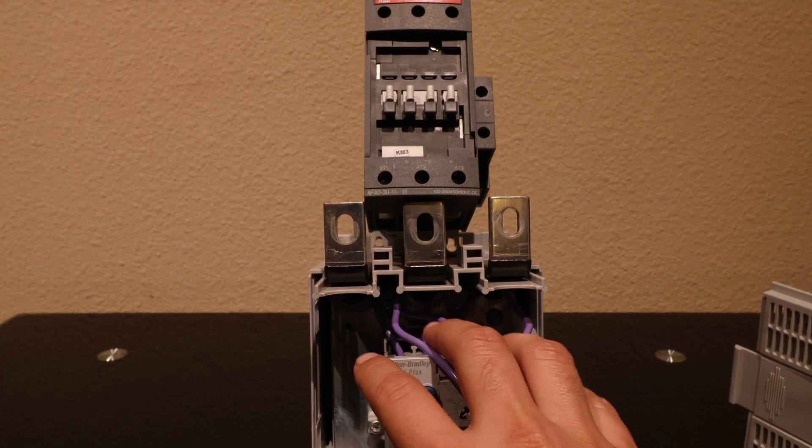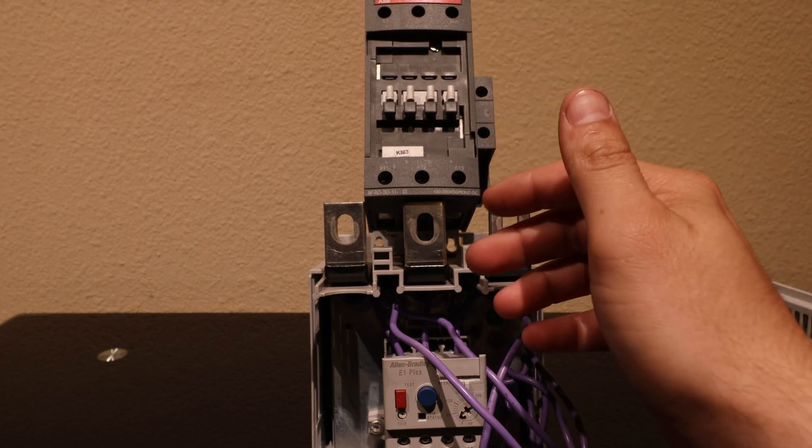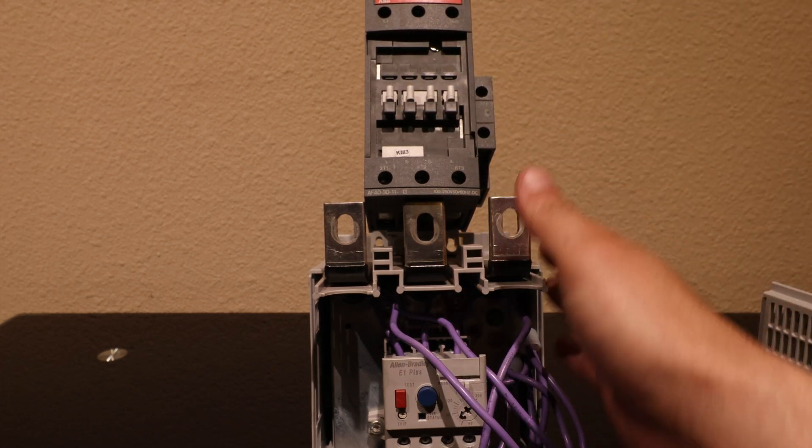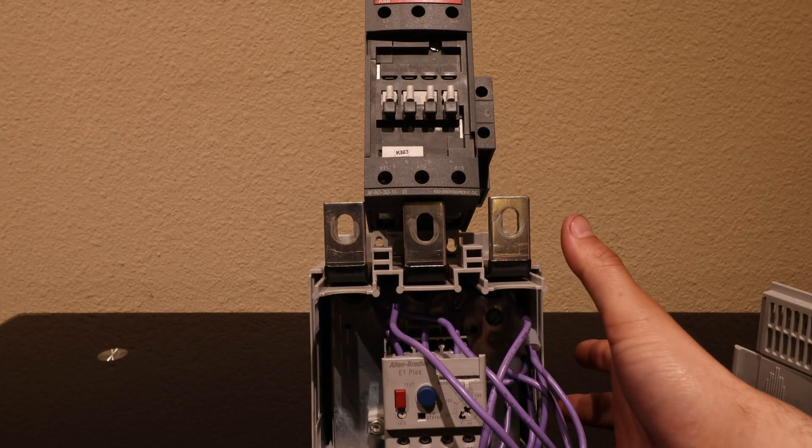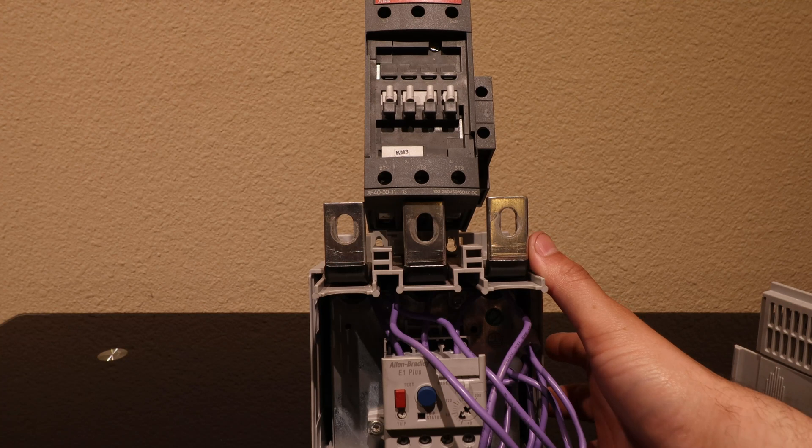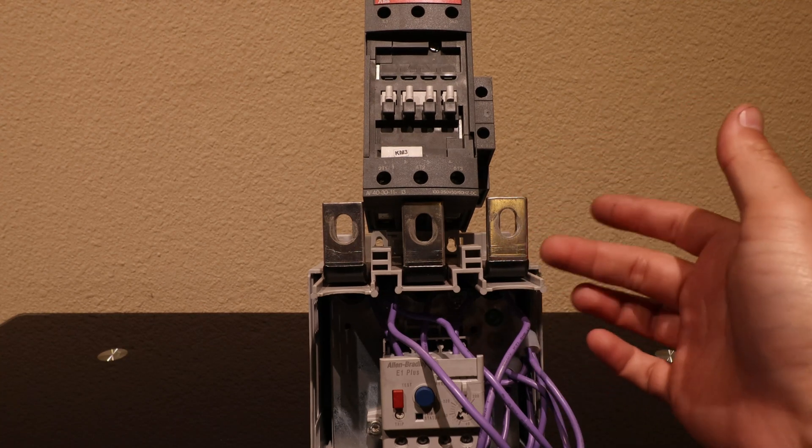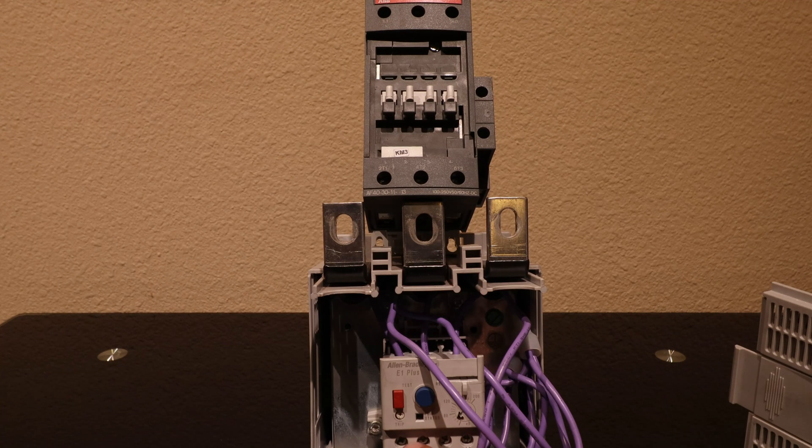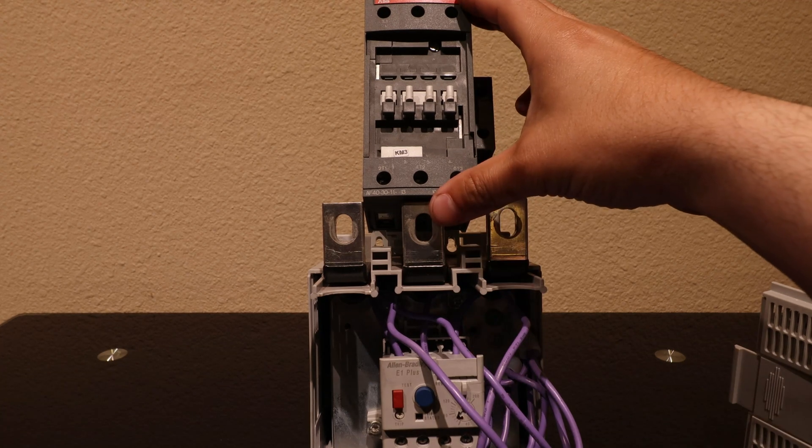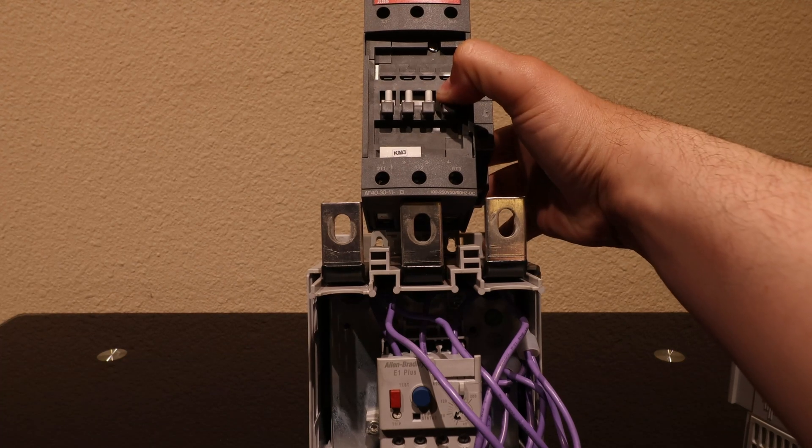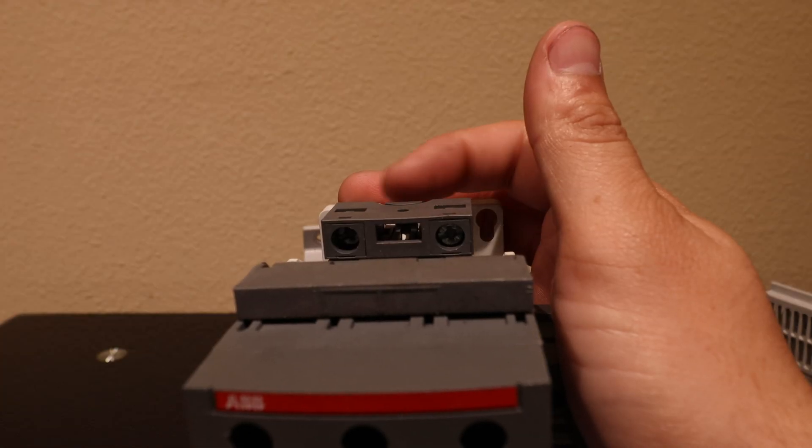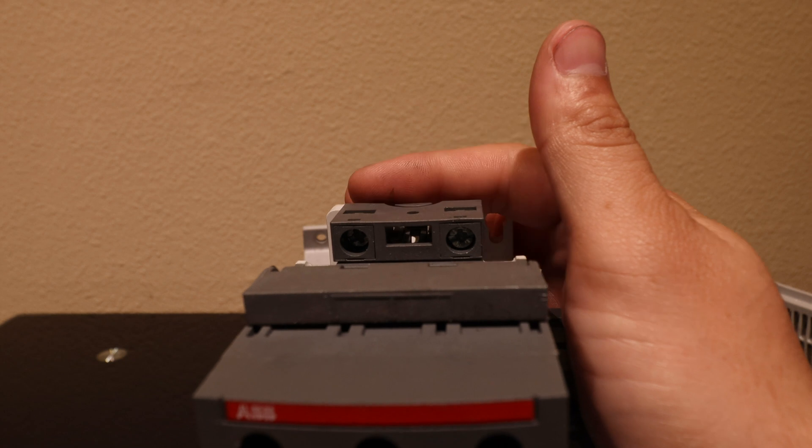I sure wish I had equal sized overloads and contactors so that this would look more legit. Normally the overload and the contactor are about the same size. Once again, since the overload doesn't disconnect the load going to the motor, it will by informing a controller or actually tripping normally closed contacts remove power from the contactor. And this contactor that was normally pulled in will then release and release power to the motor by removing the flow of amperage to one of these two points of contact.